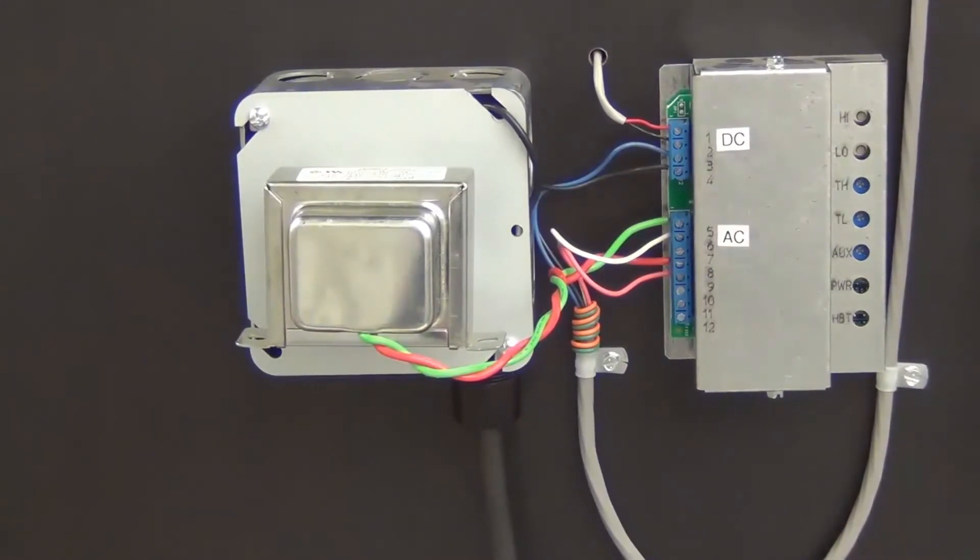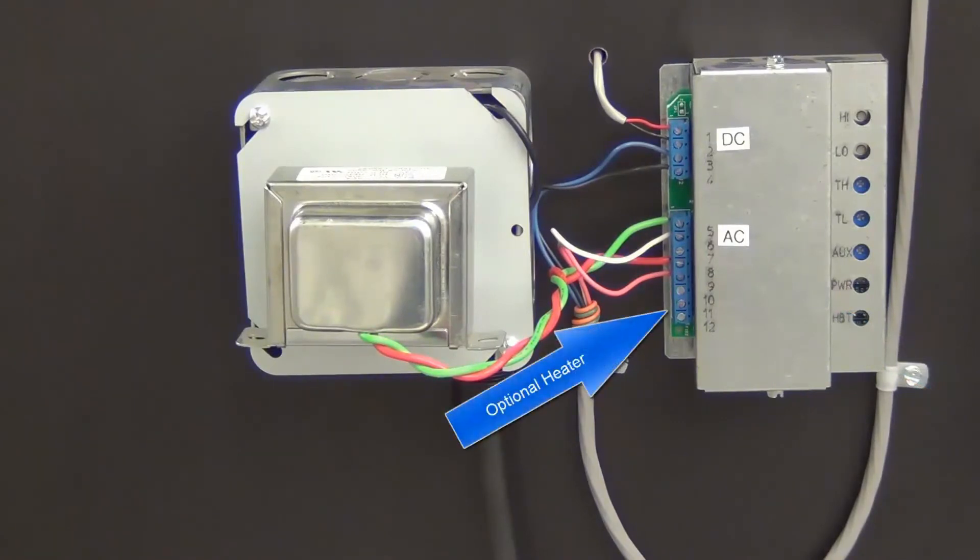The wiring connections shown in this installation are as follows: Power to the transformer, either 120 or 240 volt. Low voltage wire from the current transducer to terminals 1 and 2. Terminals 3 and 4 are low voltage DC to the EC supply fan. Terminals 5 and 7 are low voltage from the 24 volt transformer. Terminals 6 and 8 are for the low voltage connection to the ADC shutoff damper. Terminals 9 and 10 can be for an optional heater.